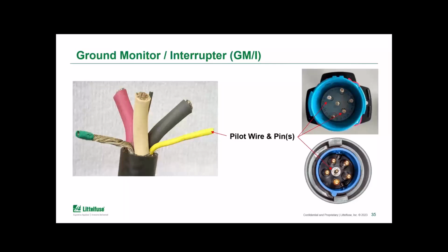And again, to recap on that point, this ground monitoring circuit is a mandatory part that was added to the Class C, D, and E special purpose GFCIs. And it's something that in the Class A GFCI standard, there is no requirement for it. So it certainly is not a required function. But there's also nothing stopping manufacturers from offering that in a Class A device if they so chose.